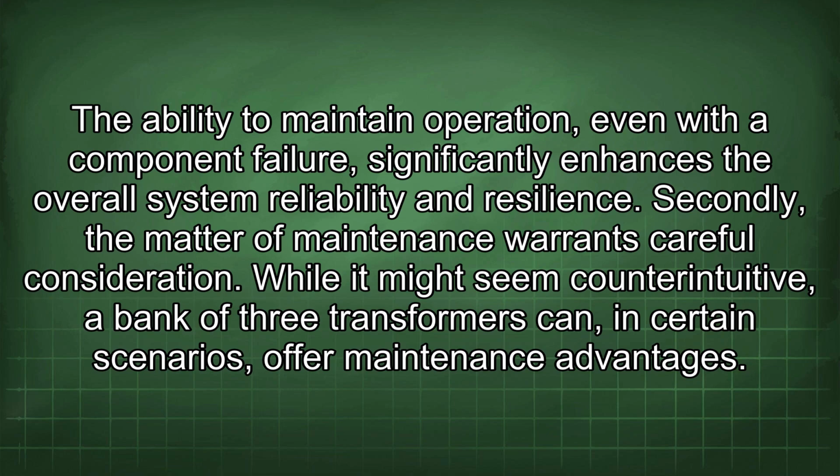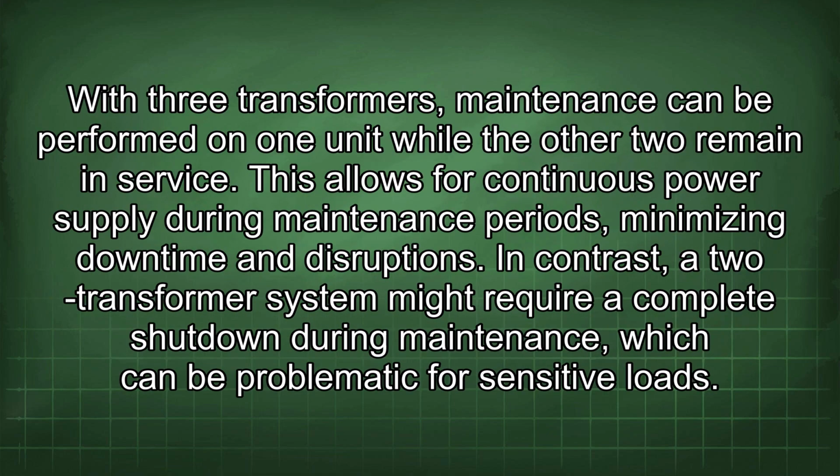Secondly, the matter of maintenance warrants careful consideration. While it might seem counterintuitive, a bank of three transformers can, in certain scenarios, offer maintenance advantages. With three transformers, maintenance can be performed on one unit while the other two remain in service. This allows for continuous power supply during maintenance periods, minimizing downtime and disruptions. In contrast, a two-transformer system might require a complete shutdown during maintenance, which can be problematic for sensitive loads.